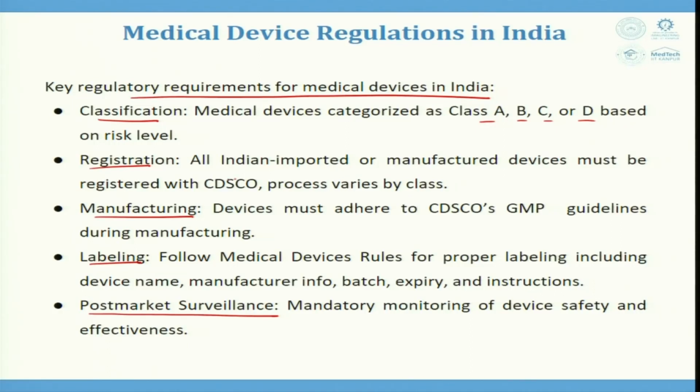Next comes registration. All Indian imported or manufactured devices must be registered with CDSCO. The process varies by class: the requirements are stringent for high risk devices, that is class D, and are lower for class A devices, which are low risk. Then manufacturing: devices must adhere to CDSCO's GMP guidelines, that is good manufacturing practice guidelines. These are taken care of during manufacturing.